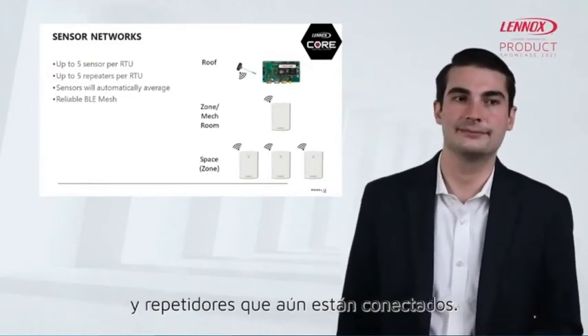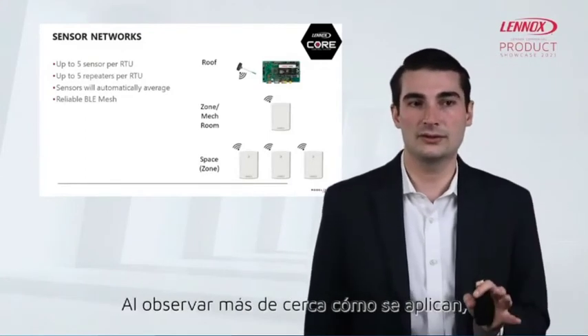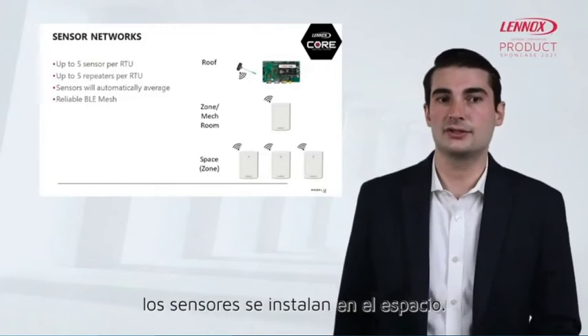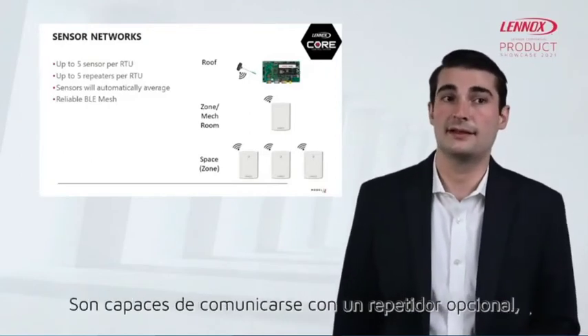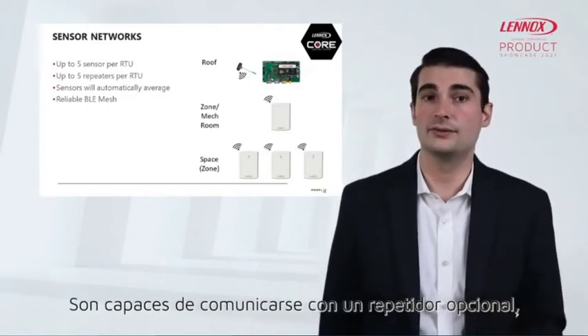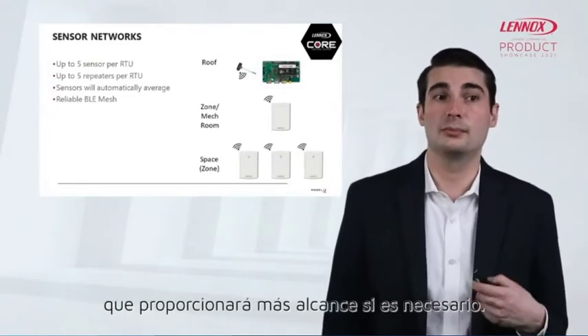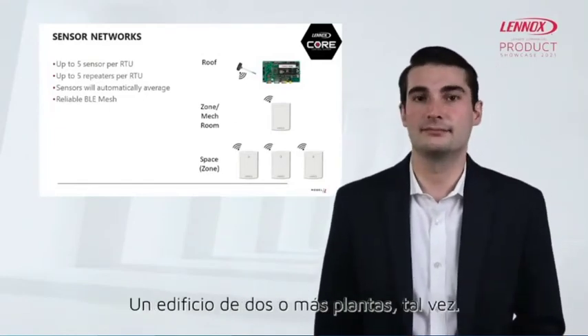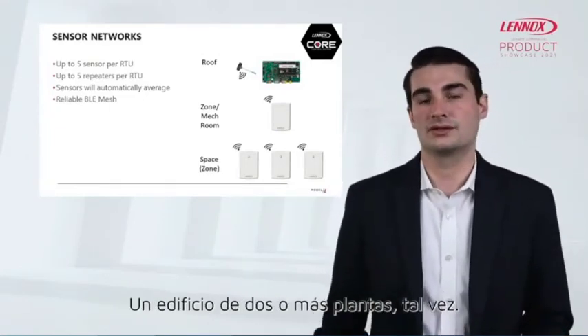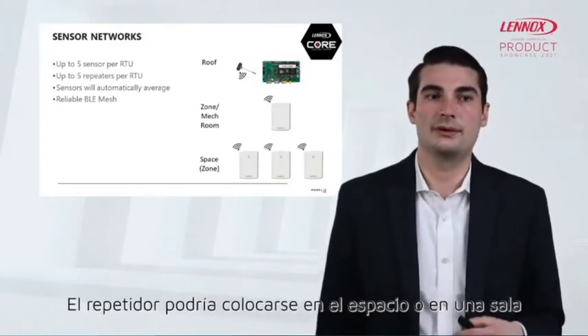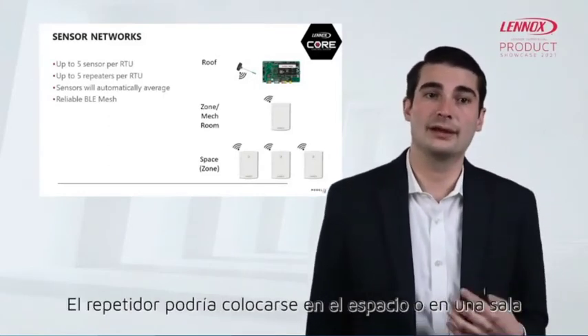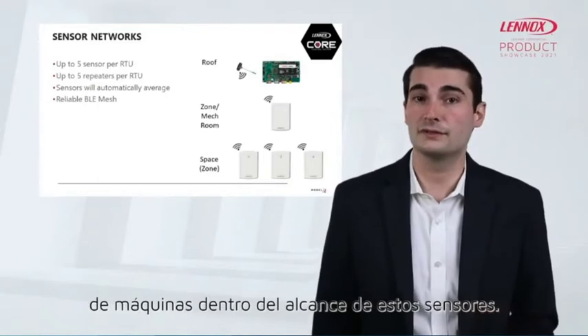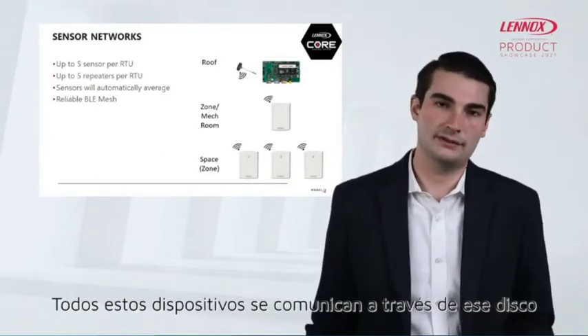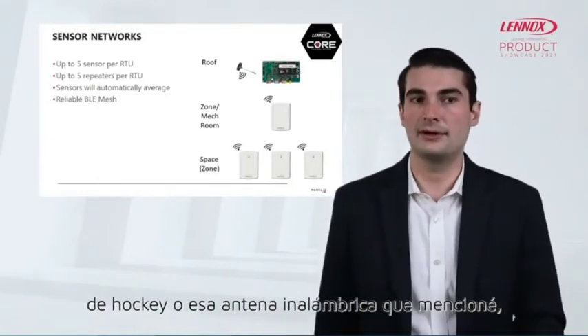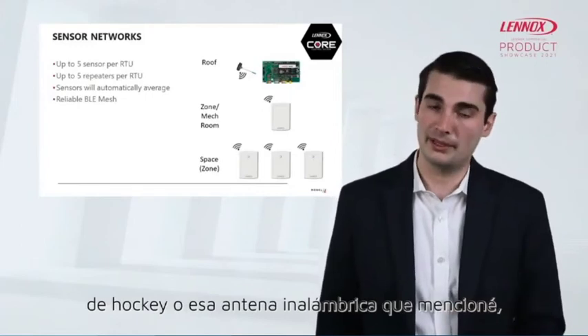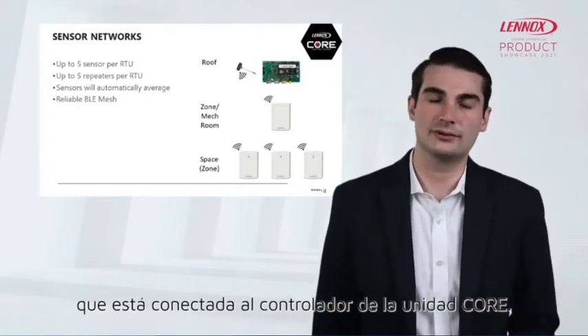Taking a closer look at how these are applied, sensors are installed into the space. They are capable of communicating to an optional repeater, which will provide more range if needed. Maybe you have a 2-story building or something taller. The repeater could be placed in the space or a mechanical room within range of these sensors. All of these devices communicate via that hockey puck, or that wireless antenna that I mentioned, which is connected to the core unit controller.